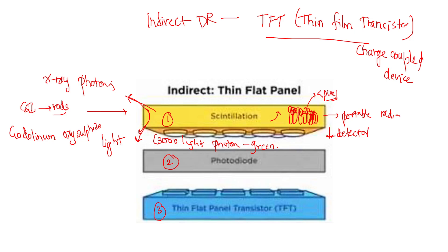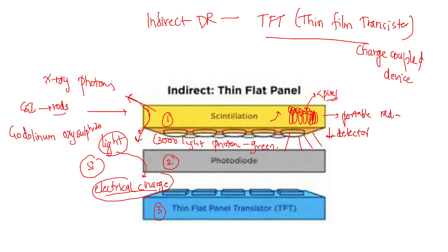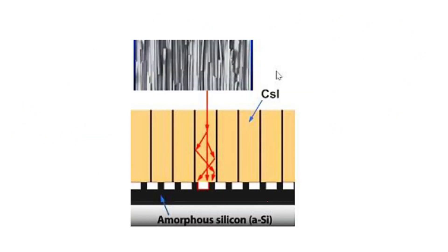A main disadvantage of scintillation is that it produces light in all directions. The photo diode detects this light and converts it into electrical charge. The photo diode is mainly made up of amorphous silicon. The electric charge produced by the photo diode is then processed by the thin flat panel transistor, which detects this electric charge.